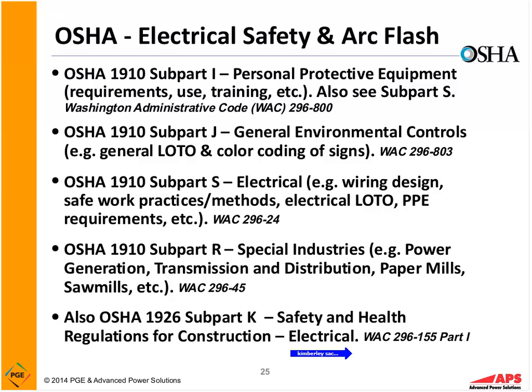Okay, subpart S, electrical wiring design, safe work practices. Now, electrical lockout tagout is specifically called out in 1910 subpart S. So if you have a general lockout tagout program and it doesn't include the provisions such as electrical hazards, testing for confirmation of the system, a zero energy state, you need to look at subpart S in OSHA 1910, whether federal OSHA or state OSHA is applicable, and include those requirements in your lockout tagout program. Of course, we also have special industries, such as power generation, transmission, distribution, paper mills, sawmills, that have additional requirements. And subpart K, we won't really talk a lot about that today, but there are some very basic electrical safety requirements for construction as well.